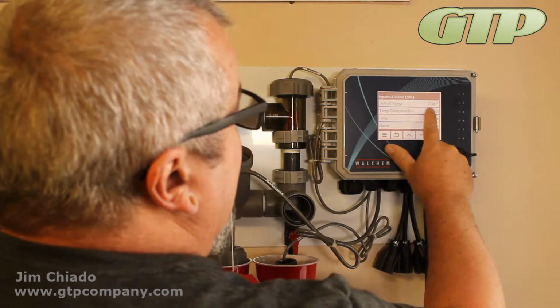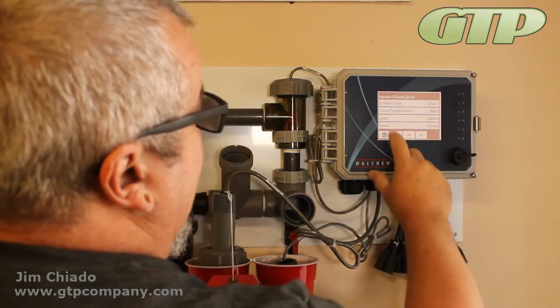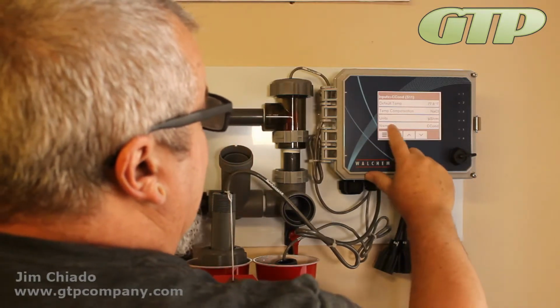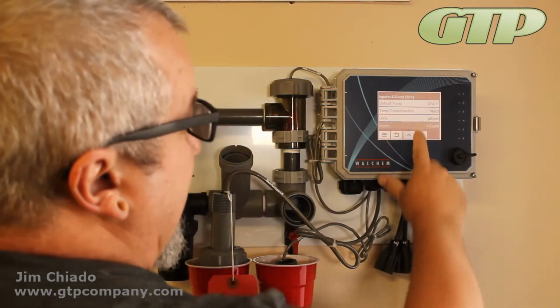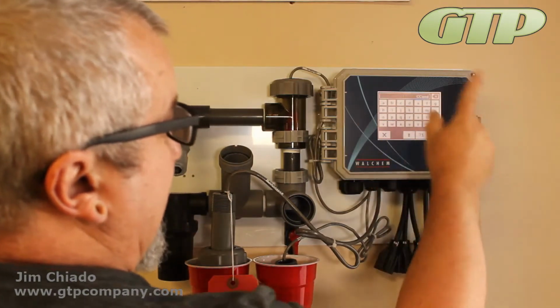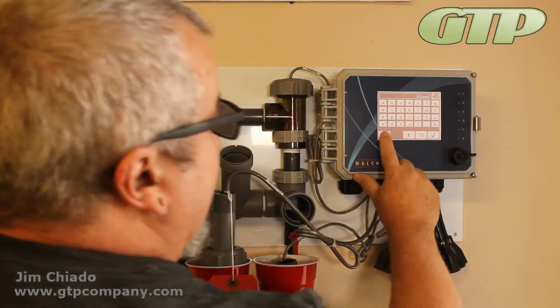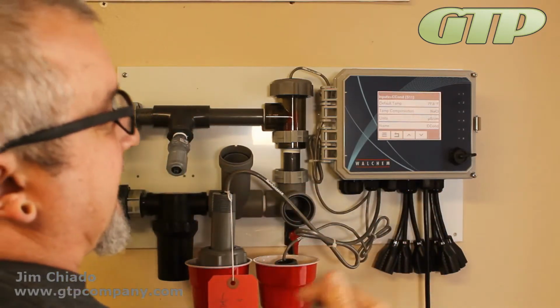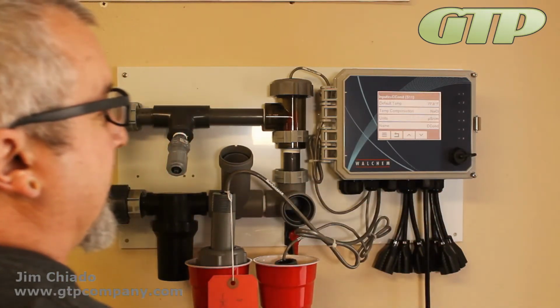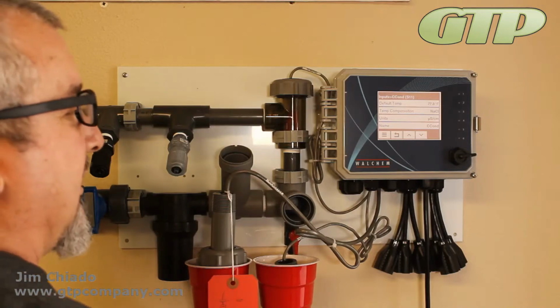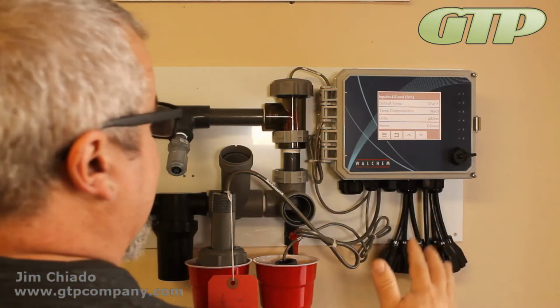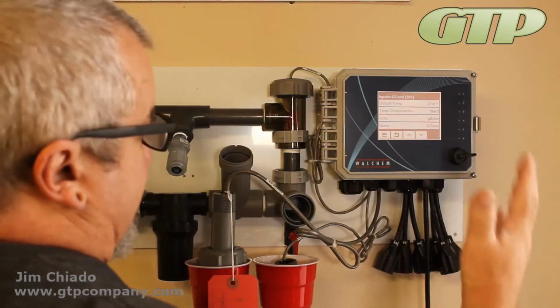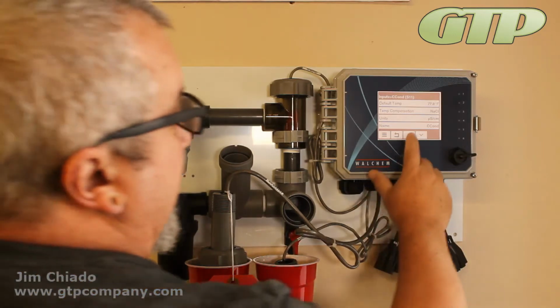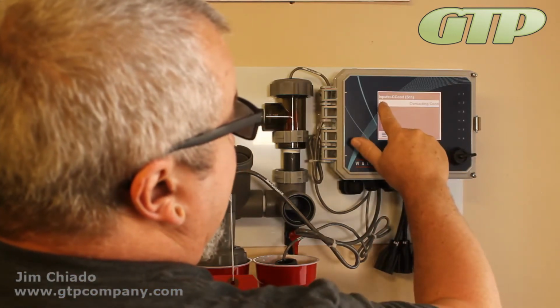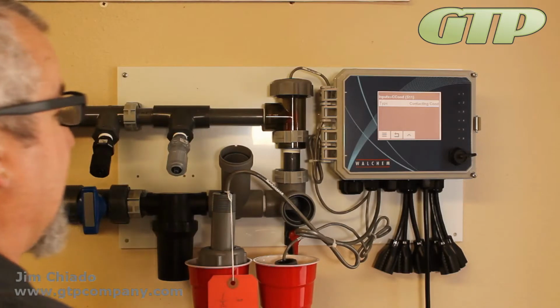Temp compensation is based on NaCl. Units are microsiemen. The name is CCON. You can go ahead and see that it does that. You can actually change whatever that's saying in there, that way you can walk up. It says CCON. CCON is Walchem's way of saying contacting conductivity. But you could just make it say conductivity, or you could make it say whatever is more appropriate for you and your client. And then the type, contacting conductivity.